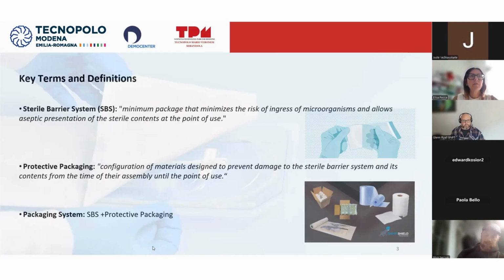A few key concepts to better understand the webinar. The sterile barrier system, also called SBS, is the minimum package that minimizes the risk of ingress of microorganisms and allows aseptic presentation of the sterile content at the point of use. The protective packaging is the additional layer protecting the sterile barrier system and its content from the time of assembly until the point of use. And the packaging system is the SBS and the protective packaging altogether.